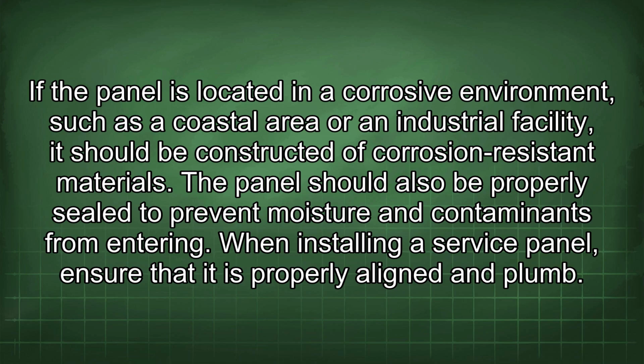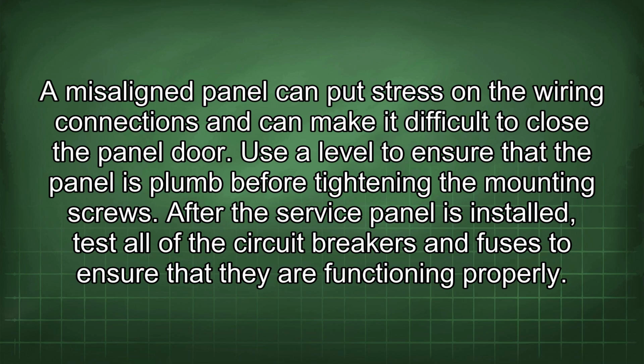When installing a service panel, ensure that it is properly aligned and plumb. A misaligned panel can put stress on the wiring connections and can make it difficult to close the panel door. Use a level to ensure that the panel is plumb before tightening the mounting screws.